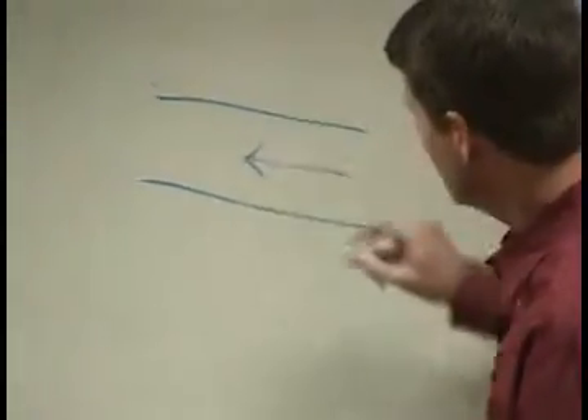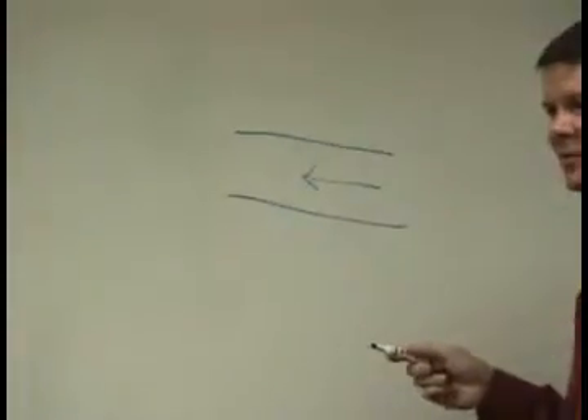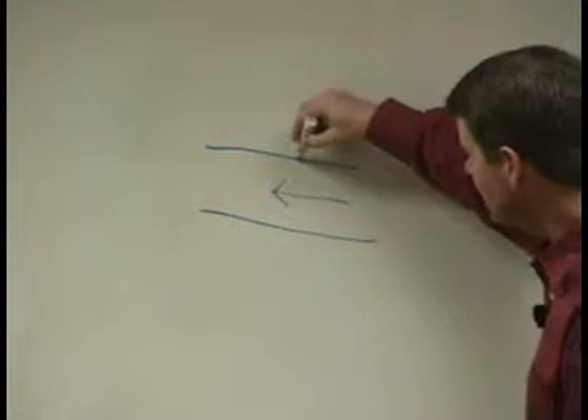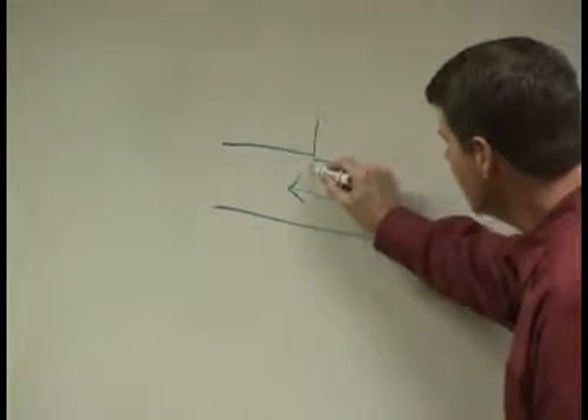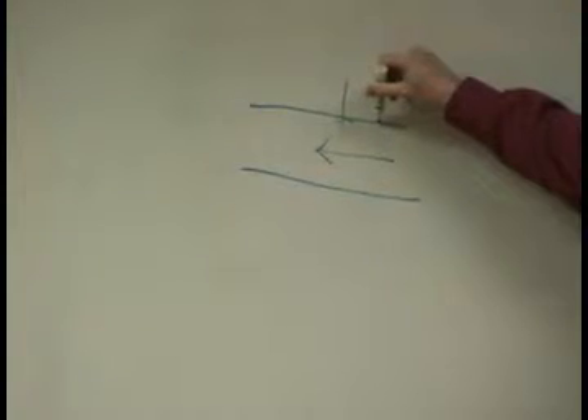So in a duct, where we're measuring air, we've got static pressure. And what is static pressure? Anybody tell me? Let somebody else answer. Static pressure is just the pressure on the side of the duct. You've got a duct here with air hurtling down it at 1,500 foot per minute. All we're worried about, static pressure, is just how much force is applied this way. If you had your supply duct, you poke a hole in it, how much pressure is coming out right there? That's the static pressure.